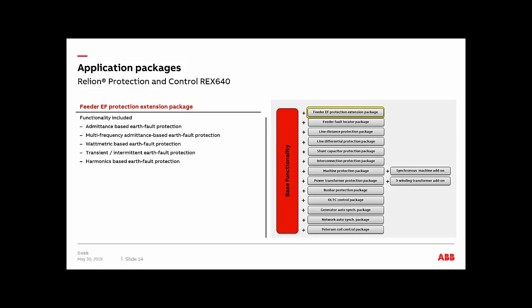Now a little bit on the admittance protection. This is going to give you a selective earth fault protection. You can use it as an alternative solution to traditional residual current-based fault protection functions. And it's got the advantage of being fairly easy to set up and very sensitive to ground faults. It can be applied as well in high resistance grounded, ungrounded, or compensated networks.